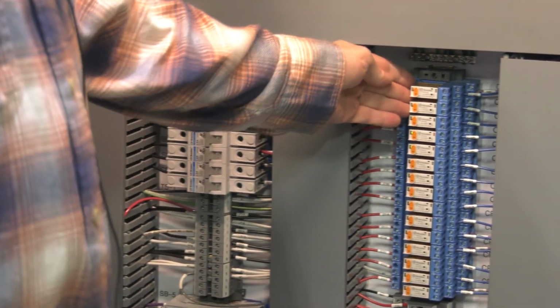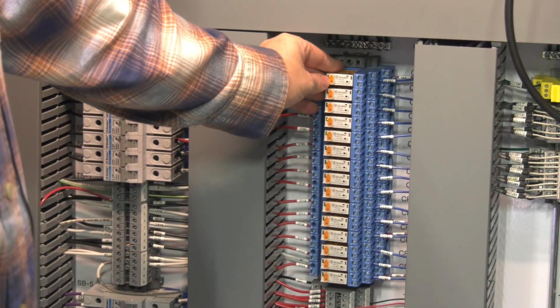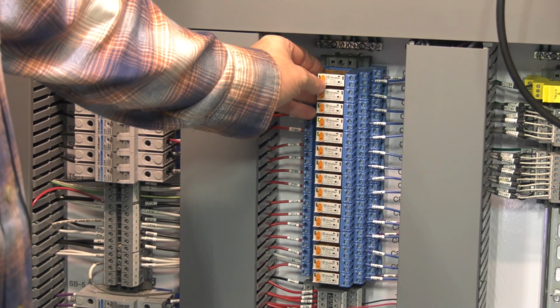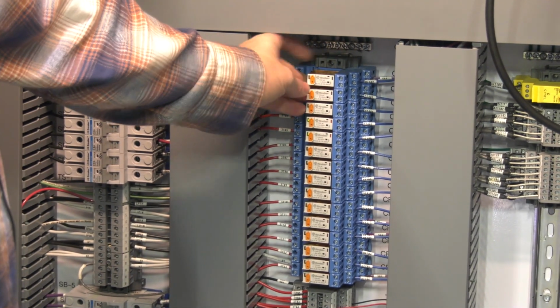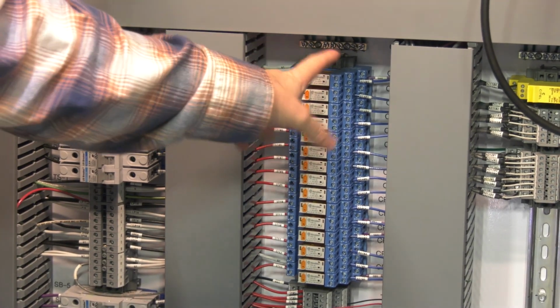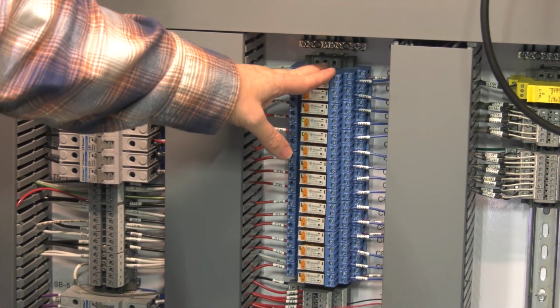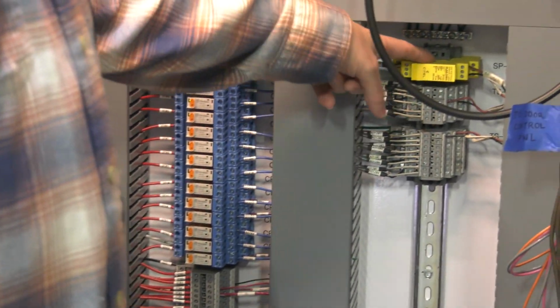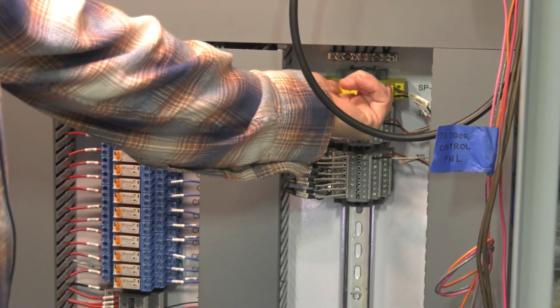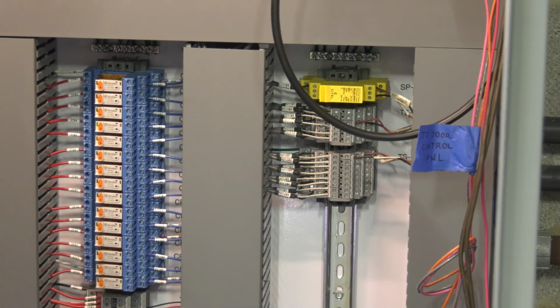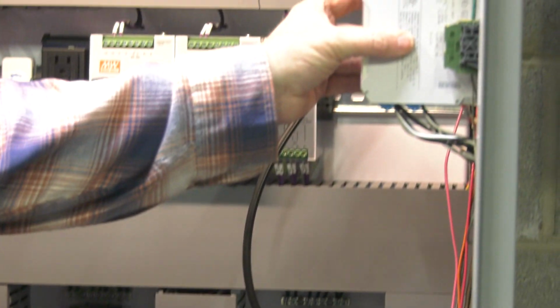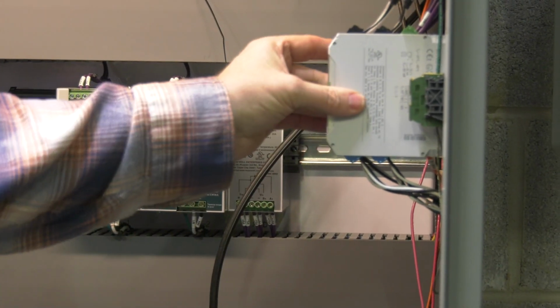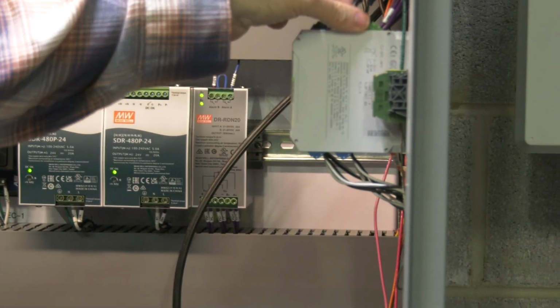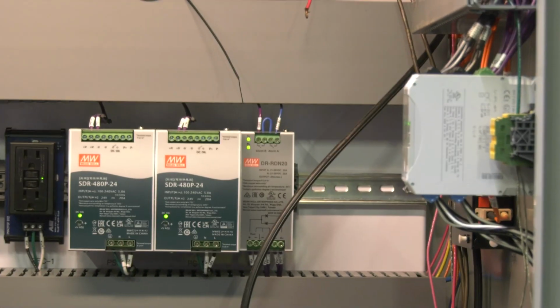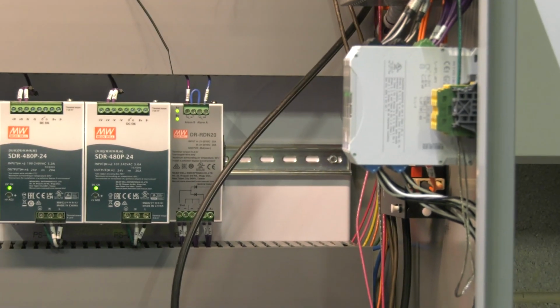Let's see, here's your relays. You can push the orange button to temporarily turn the relay on, or you can turn this flag and it'll turn the relay on, keep it on, forced on. Here you've got the analog surge suppressor. Again, the module pops out and can be replaced. Here we've got our intrinsic safety barriers. If one needs to be replaced, these terminals pop off. It can be easily replaced. There are no configuration dip switches to be set.